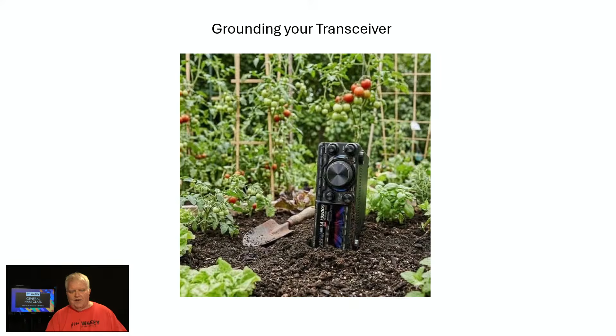For grounding, you need to know that grounding has different purposes in mind, and there's at least 3. There's electrical safety - that's one type of grounding, and local electrical codes apply for electrical safety. Then there's lightning protection, either to prevent damage from a direct lightning strike, or more commonly to dissipate energy from a static charge in the atmosphere so you don't have a lightning strike.